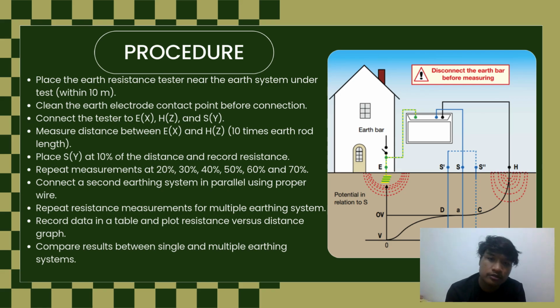Alright. Next, I will explain the procedure. As you can see in the diagram at the right, it is the connection of this earthing, grounding the cable in parallel to get the minimum ohm. The first procedure is to place the earth resistance tester near the earth system under test, within 10 meters. You have to clean the earth electrode contact point before connection to prevent dust and any problem. Connect the tester to EX, HZ and SY.